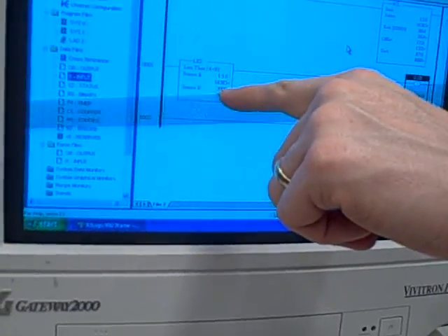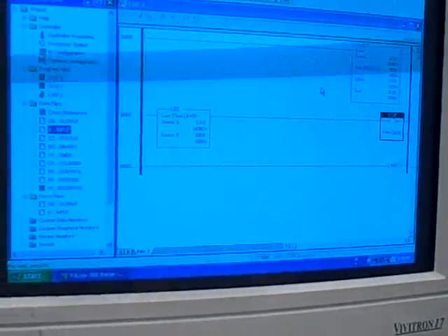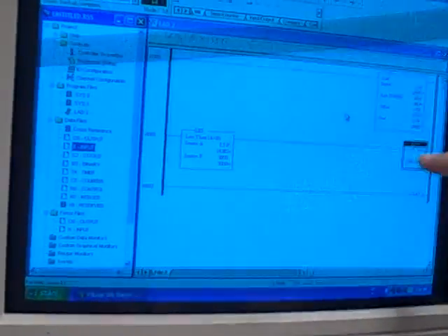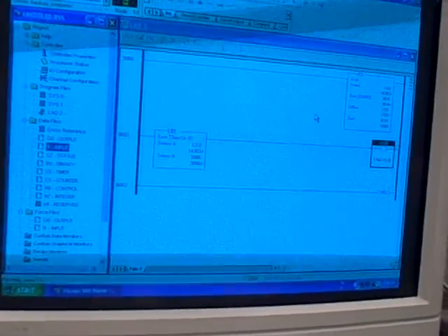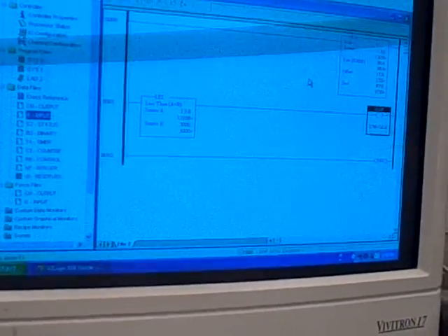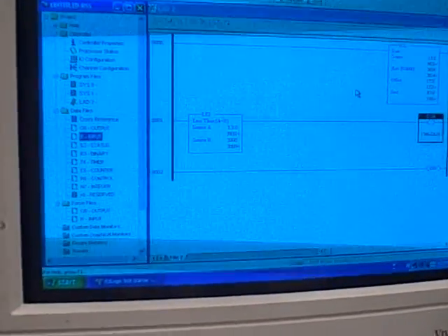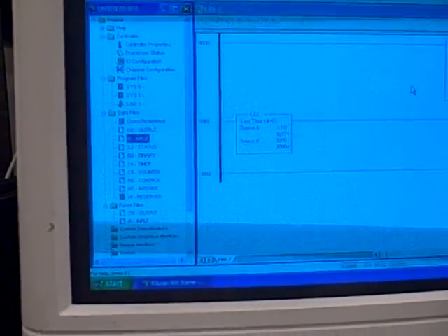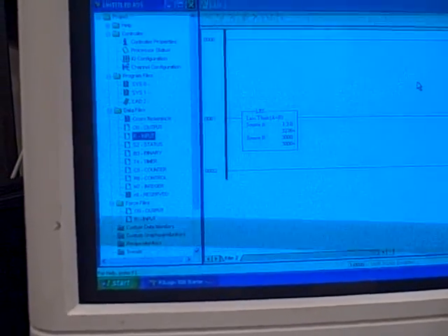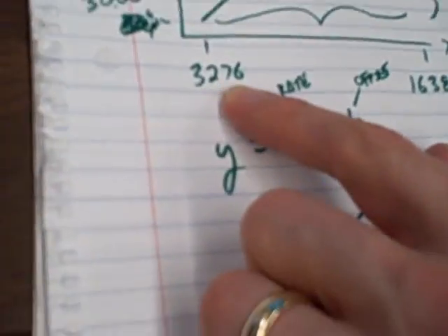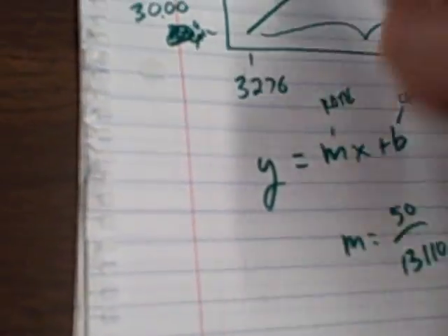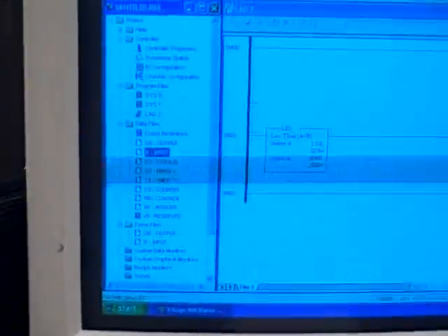We're comparing that against a fixed value of 3,000. If I drop below that, I want to turn on that output. So I'm going to go down, 16 milliamps, 12 milliamps, 8 milliamps, 4 milliamps. Here we are, bottom of the scale, 4 milliamps, a count of 3,276. We're still above the limit of 3,000, so we haven't turned our output on yet.